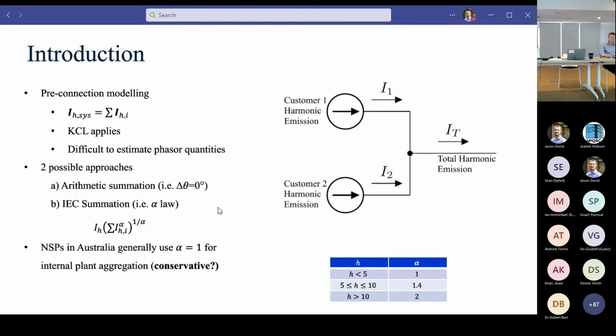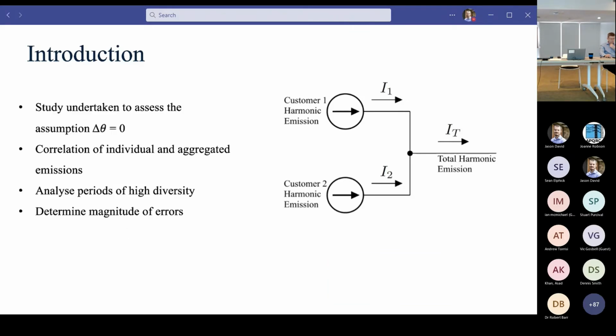So anyone familiar with 61000-3-6 will be aware of the alpha law or the summation law, and this ultimately attempts to build in some statistical diversity into the process itself, assuming that some degree of diversity exists between individual harmonic sources. However, most commonly in Australia, when undertaking harmonic emissions assessment, and I'm talking about pre-connection compliance assessment, we assume that there is no diversity between identical sources, which may be a fair assumption to make on the face of it.